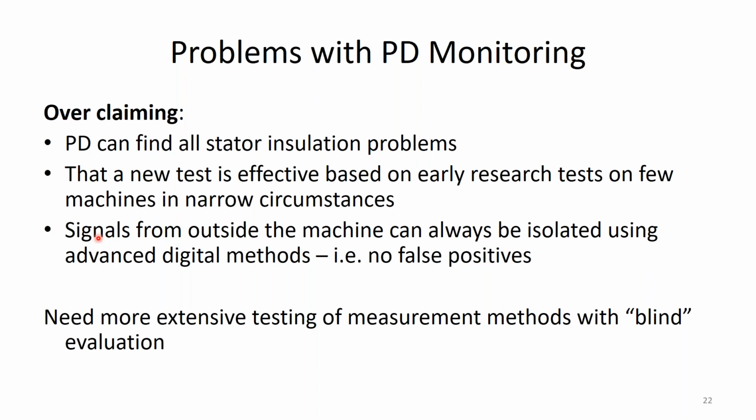Many people now, especially because it's easy to do post-processing and data manipulation afterwards, are saying, hey, we can detect all or separate out all noise. And that's not true. Okay, there are still false positives, even with us. I didn't get into it in detail, but we use 4 independent ways of separating PD from noise.